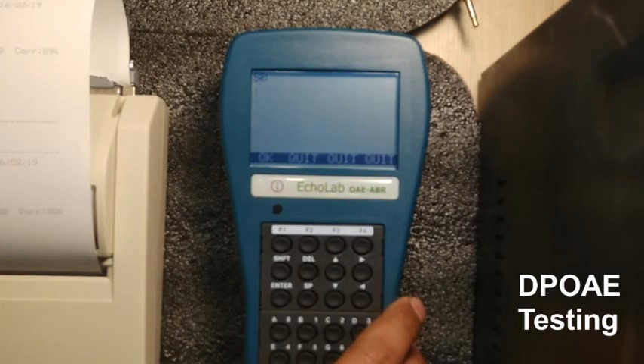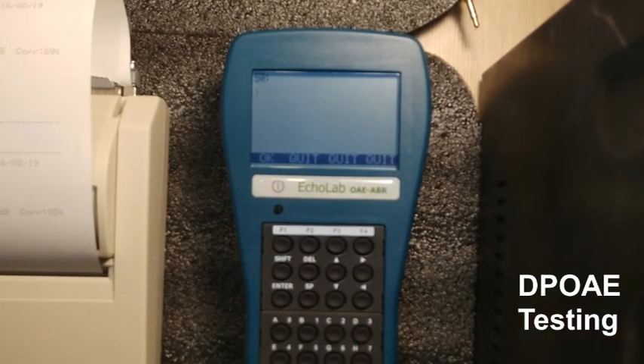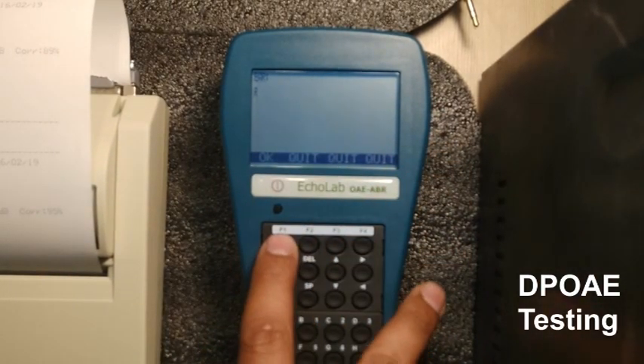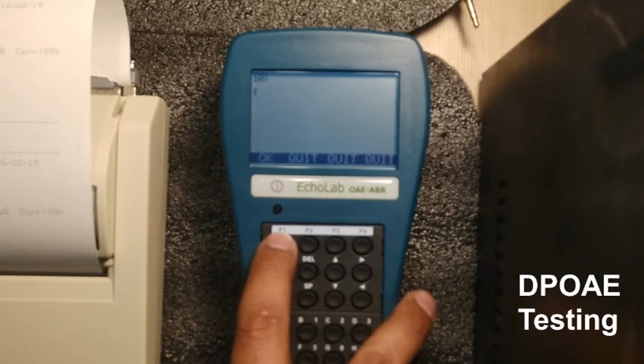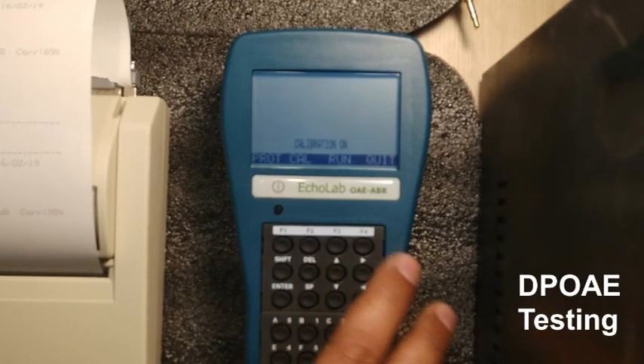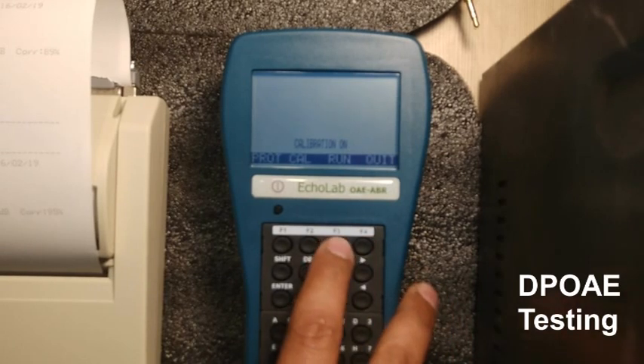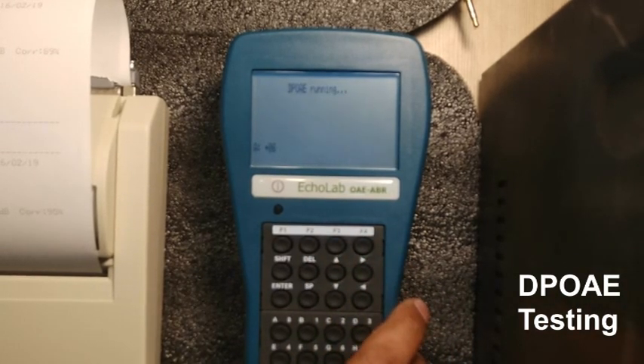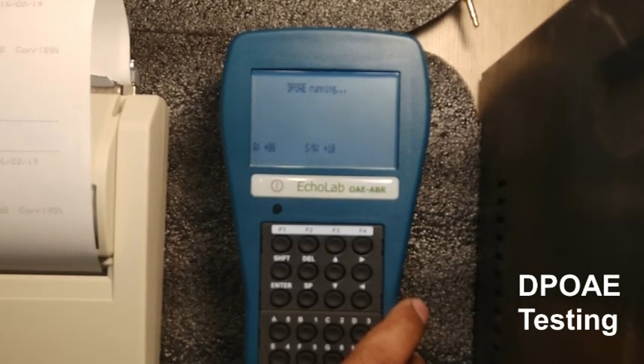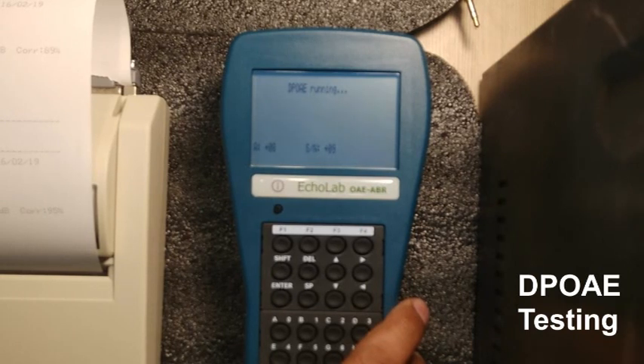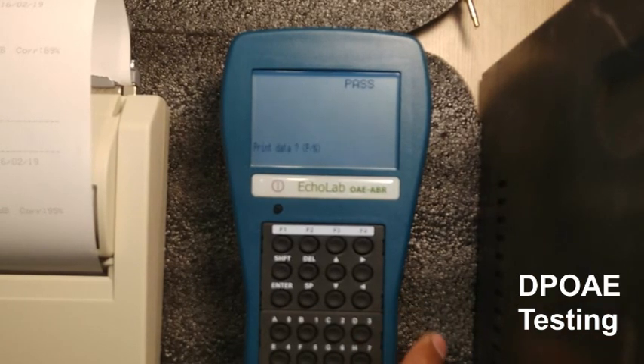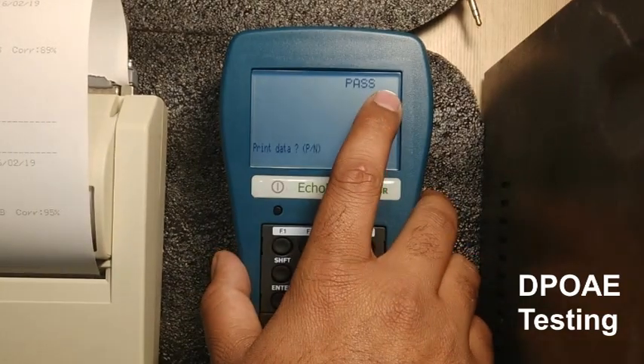Now at this time you have to put the probe in the patient's ear and select the ear in which you have put the probe. So I'm putting it in right. So now I have pressed R for right. At this time you press F1. At this time you will hear a sound and then run. So now the test is done. You can see it shows pass.